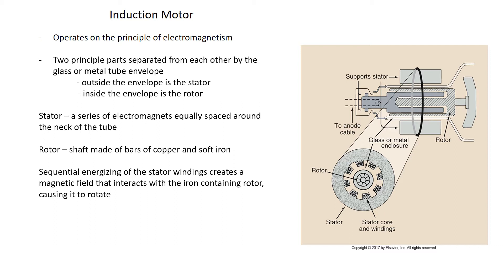The anode turns through sequential energizing — one electromagnet turns on then off, the next turns on then off, and so forth around the tube. The sequential energizing of the stator windings creates a magnetic field that interacts with the iron-containing rotor, causing it to rotate. The electricity can energize these electromagnets very quickly, rapidly spinning the anode.